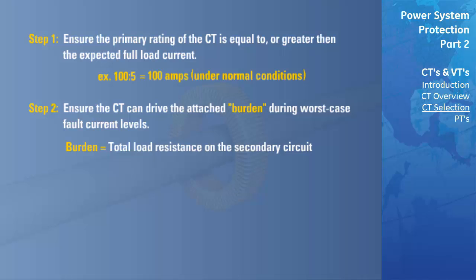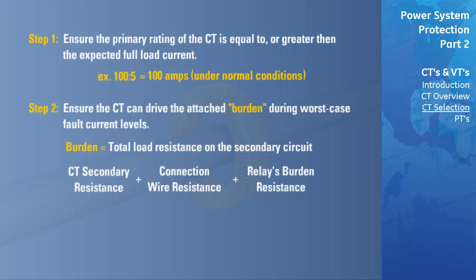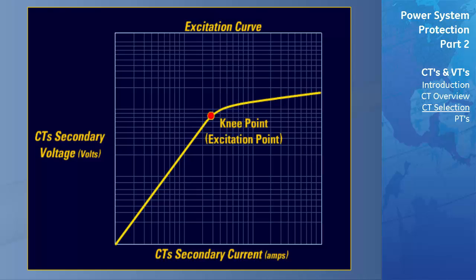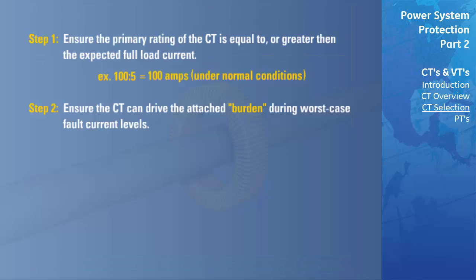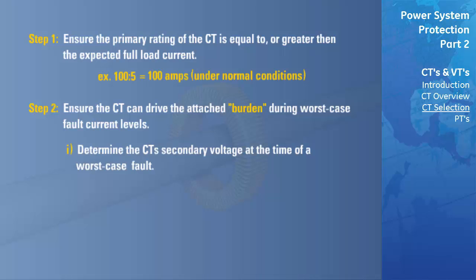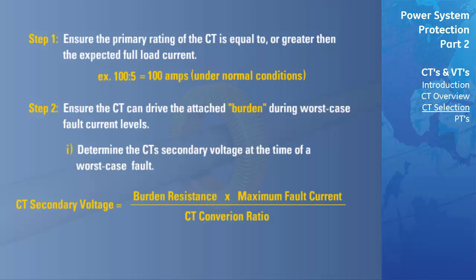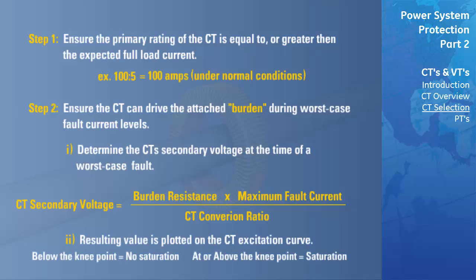The burden refers to the total load resistance of the secondary circuit. The calculation for the burden is the CT secondary resistance — the amount of resistance on the secondary windings — added to the connection wire resistance, added to the relay's burden resistance. A CT becomes saturated when the voltage secondaries reach the knee point of the excitation curve. To determine whether the CT can drive the attached burden under worst case fault conditions without saturating, we must determine the CT's secondary voltage at the time of the fault. The CT secondary voltage at the time of fault equals the burden resistance times the maximum fault current divided by the CT conversion ratio. The resulting value is then plotted onto the CT excitation curve. If the value plotted is below the knee point, the CT will not saturate; if it is equal to or greater than the knee point, the CT will saturate.